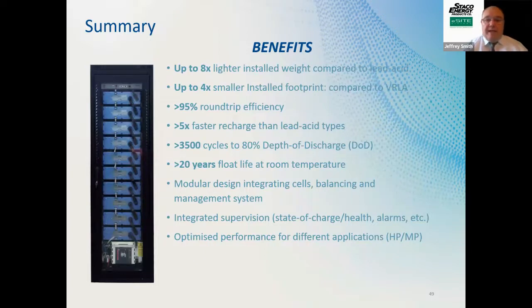You can see the benefit: up to 8 times lighter than installed weight compared to VRLAs, and a smaller footprint. Sometimes one cabinet filled with lithium replaces 2 or 3 cabinets of VRLA for the same power. There's also faster recharge time, 3,500 cycles to 80% depth of discharge, and 20 years float life at room temperature, so if you don't use your system much, it can last a lot longer than normal. It's optimized for high power and medium power applications.